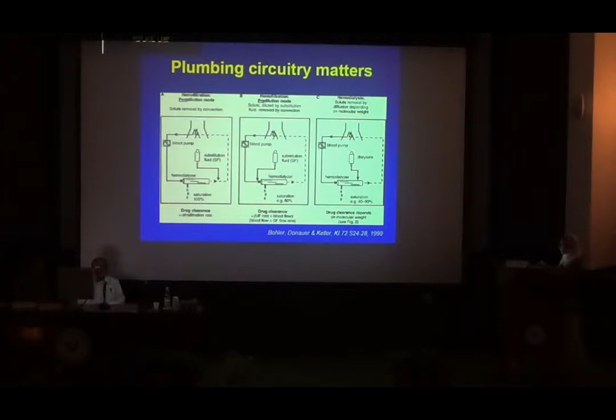Whereas if it is in the pre-dilution mode, the saturation is going to be reduced because of the passage of the replacement fluid with the blood in the hemofilter, and this will have to be corrected by using the second formula, which takes into consideration as well the blood flow rate and the replacement fluid flow rate. Whereas in the case of hemodialysis, the clearance would depend more on the molecular weight.